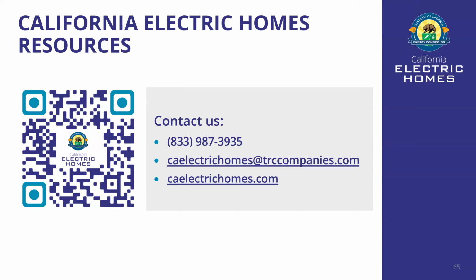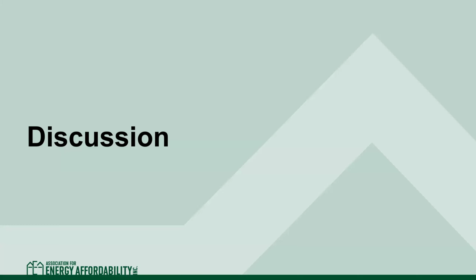All right. Some of them have been answered online, but this one has not. Have any analyses been done for large tank, small compressor scenarios on the benefits of added exterior insulation sleeves and such on the tanks? Yeah, I don't know of any specific studies on that scenario. I mean, if you're installing everything outside, it's important to have tanks that are outdoor rated, which often have more exterior insulation. I don't know that adding extra insulation that's not already there would do too much. There are standby losses in the tanks when there's not hot water use, but I don't know how significant tank insulation would be on that.